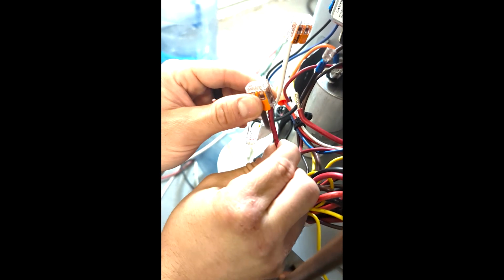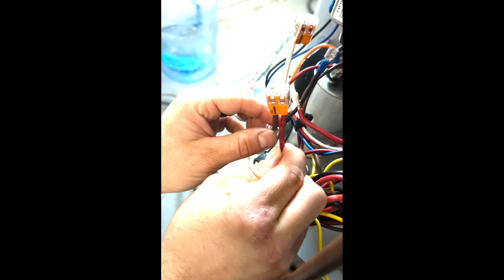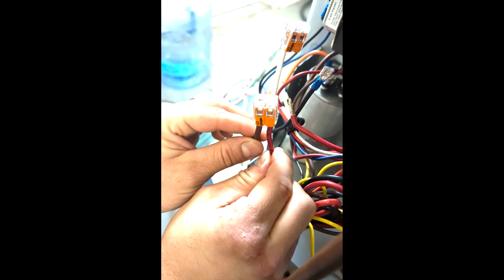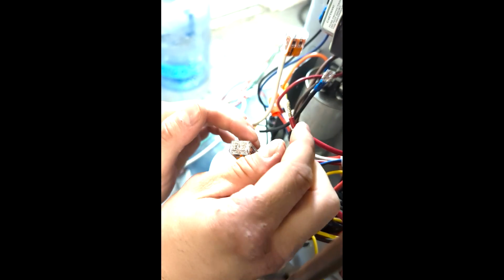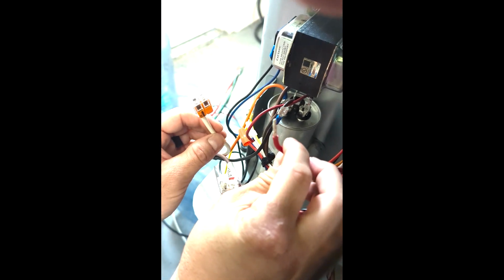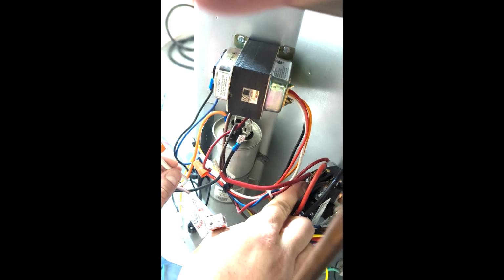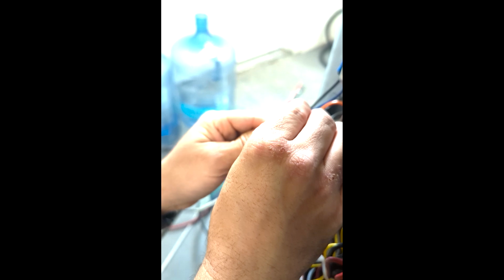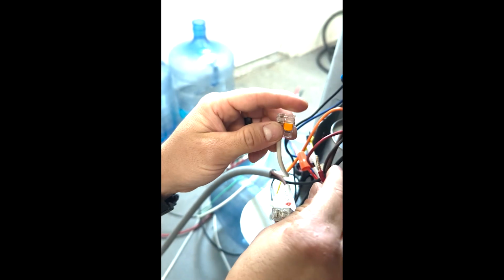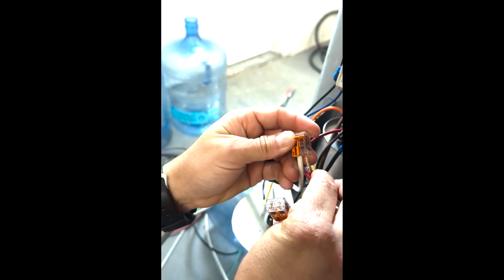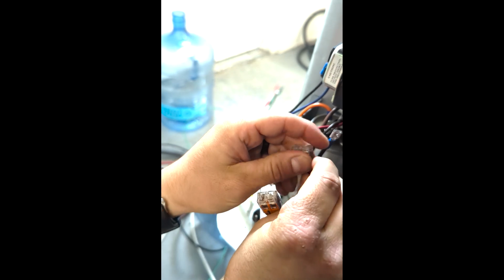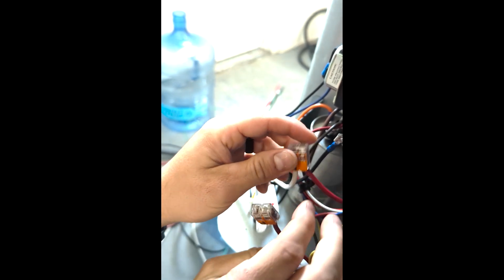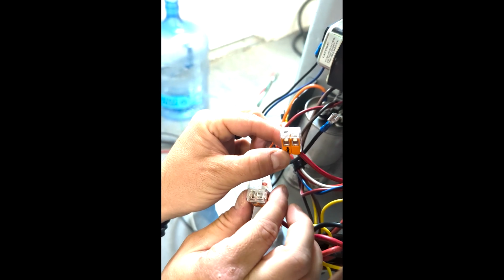So the one wire that you cut that goes back to the compressor goes to the brown wire on the EasyStart. Now, the other end of the R wire that you cut, the one that goes to the contactor, goes to the white wire on the EasyStart. Same concept: you flip the tab up, you stick it in, and you shut it down. Do a little tug, make sure it's good. So there you go, those two wires are connected.